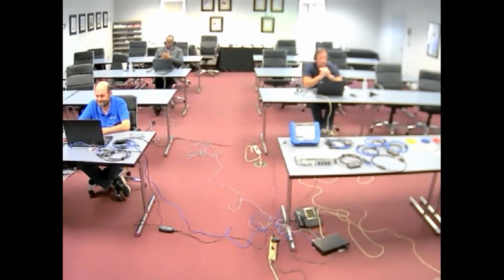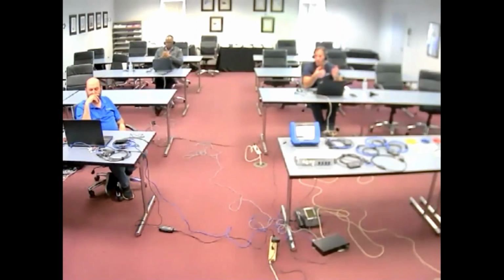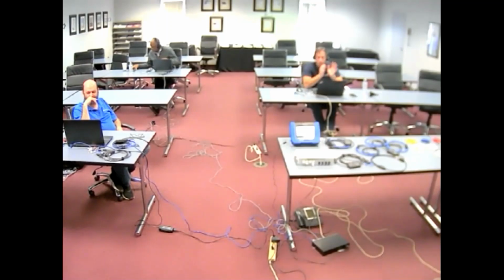Just a second thing to add to what Thurman said: when you're remotely configuring the instrument, be very careful with the IP address, because you're already configured for IP communications and have established that connection. But if you go ahead and change that IP address, now you've locked yourself out of that instrument. You would need to reconnect, and it has to be a proper IP address that you enter. So just a word to the wise there.